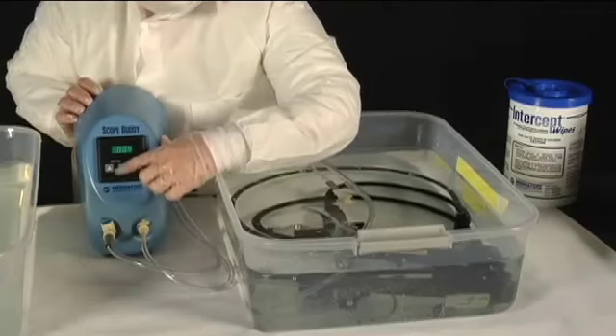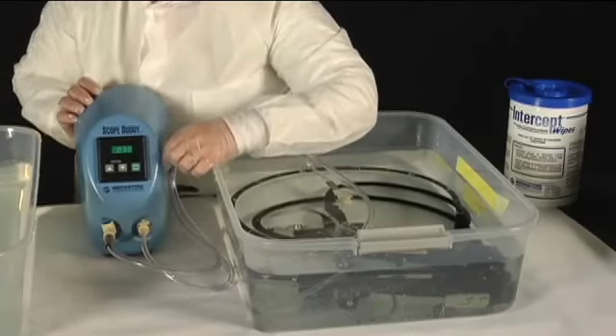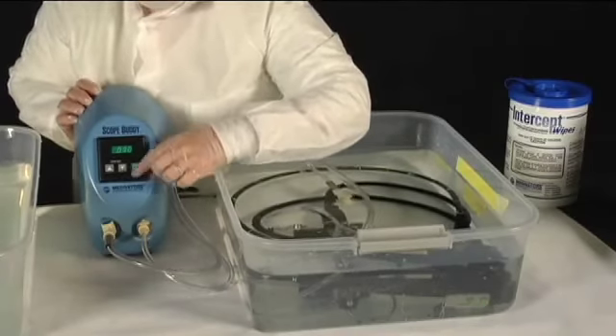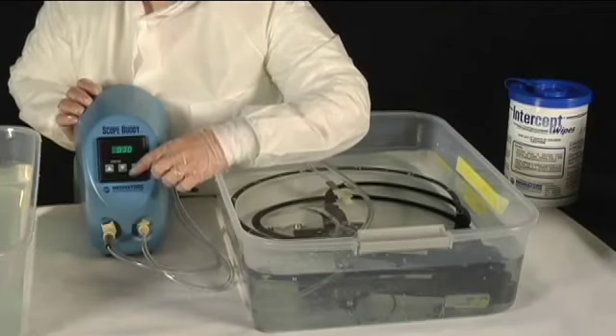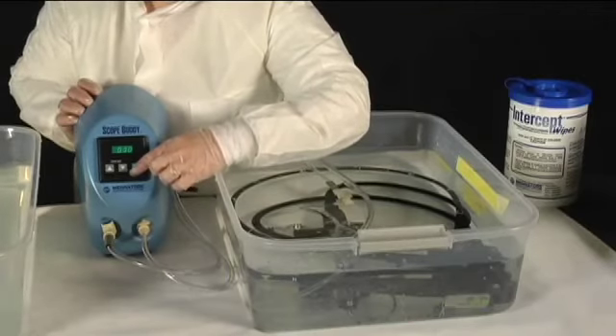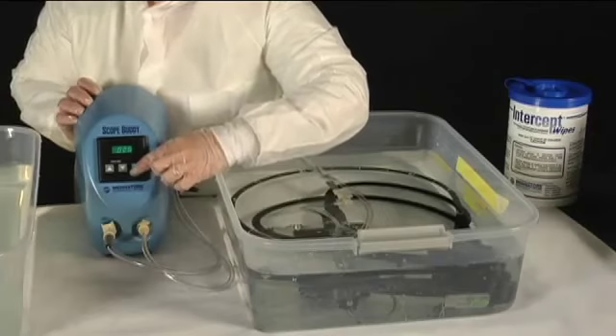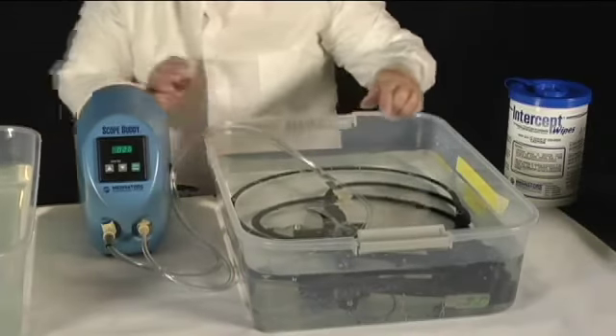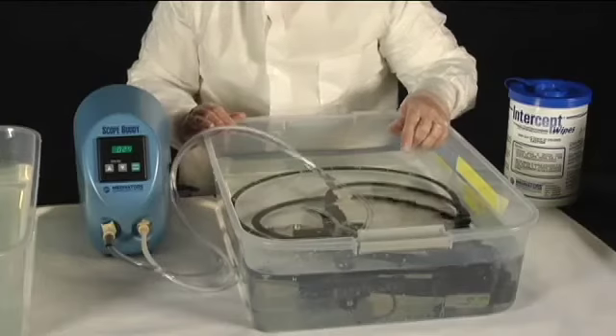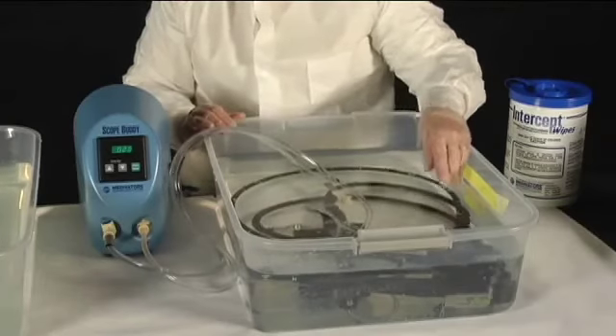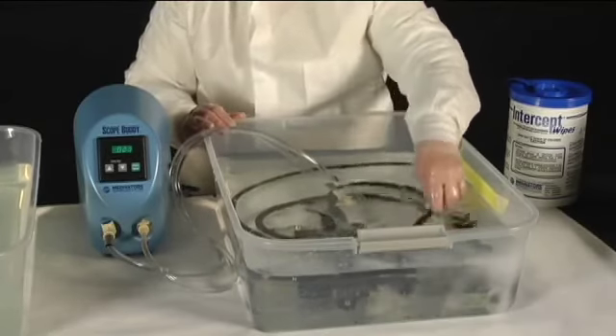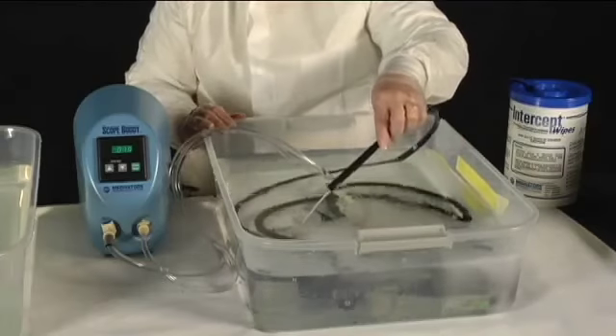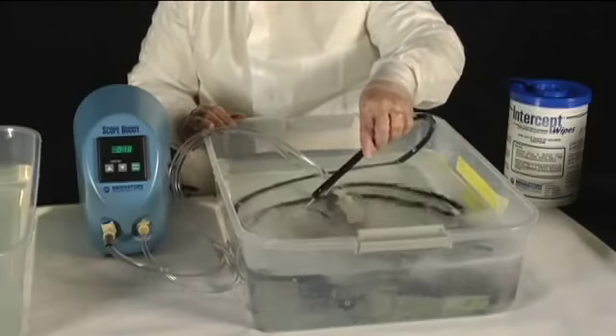Press either the arrow up or arrow down button once to reset the timer to the original preset time amount. Press the Start-Stop button to begin the cycle. The timer display will now begin counting down. Rinse water will now be drawn up from the sink or clean supply container, pumped through Scope Buddy, and will flow out the endoscope distal tip. After the timer counts down to 0, fluid flow will stop and an audible tone will be heard.